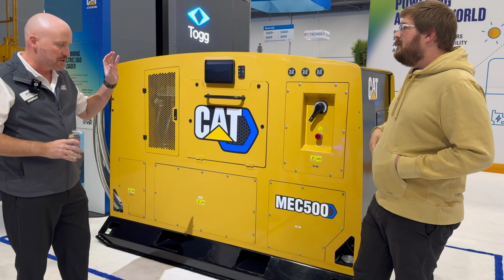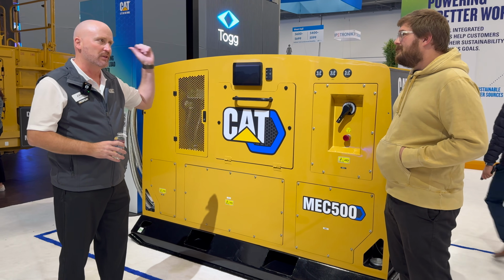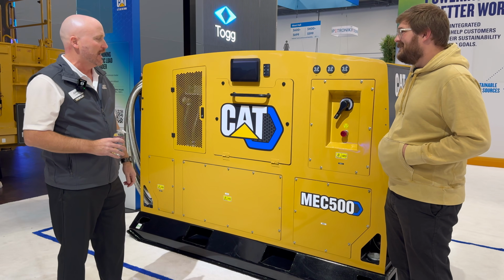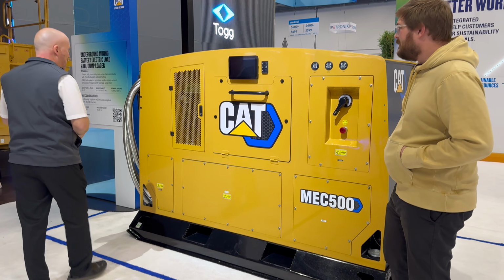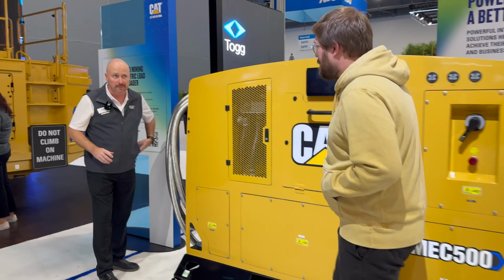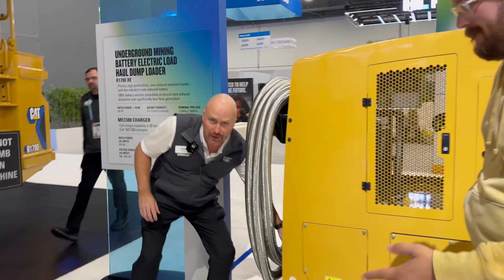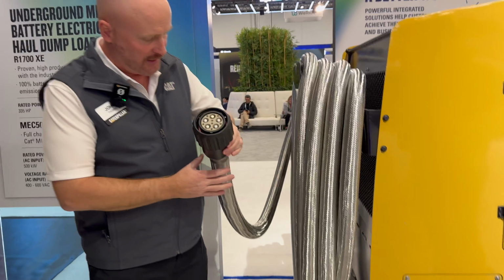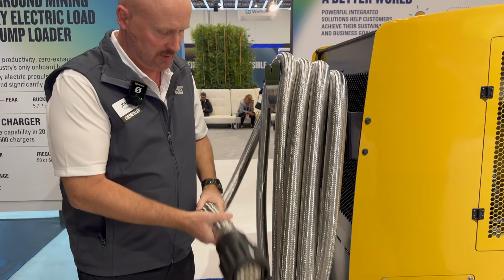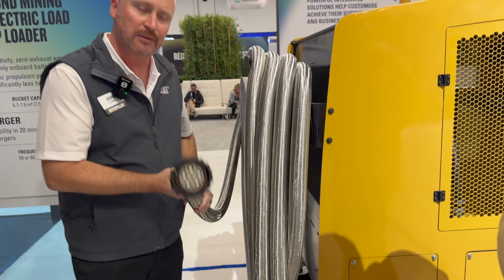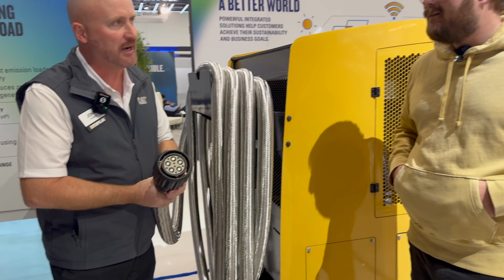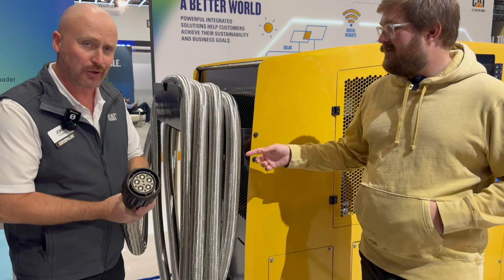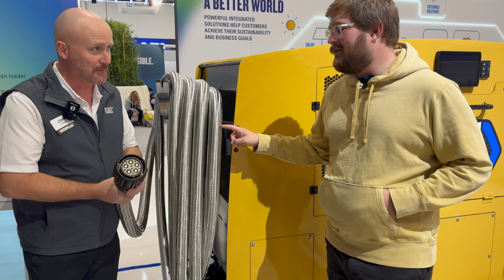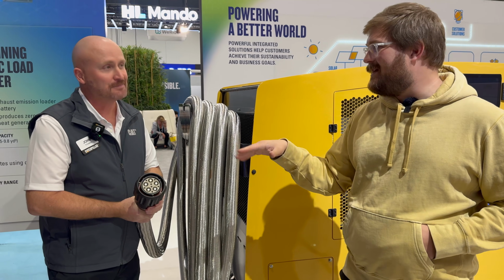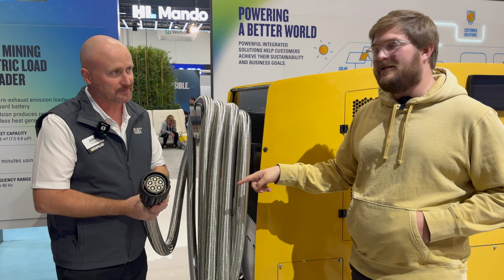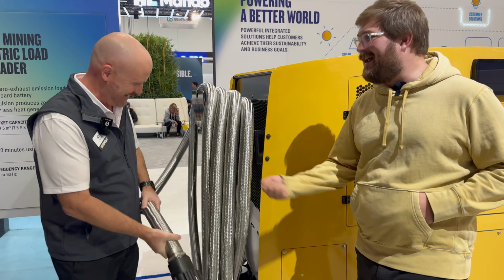This unit was specifically designed to support the beautiful machine we're about to look at in a second, and there are some really interesting things about it. One is that we developed a proprietary connector that's actually passively air cooled, so the cable is relatively flexible. We can pass 700 amps continuously through this passively air cooled cable and connector — a non-liquid cooled 700 amp cable that's still easier to manipulate than the liquid cooled 500 amp ones we see elsewhere.